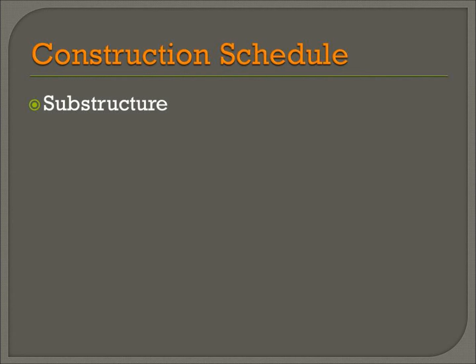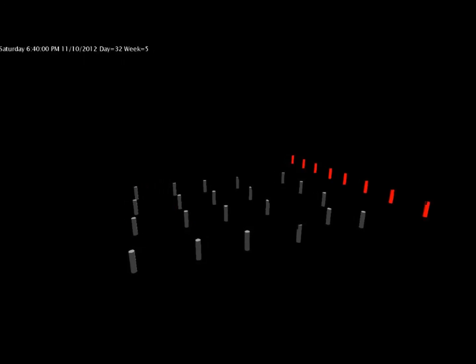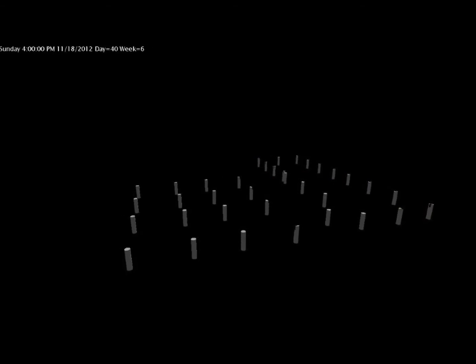Substructure schedule. The first step is to drill and place the 24-inch piers, starting with those on column line 21, followed by column line 22, and so on. The piers are filled with concrete and steel the day they are placed to avoid having open holes on site for safety reasons. The depth of the piers varies depending on when the soil reaches a specific bearing capacity. The piers for the transformer yard and chiller tower will be placed following the main structure's piers.